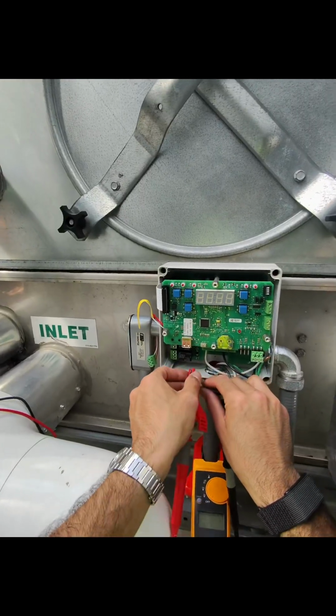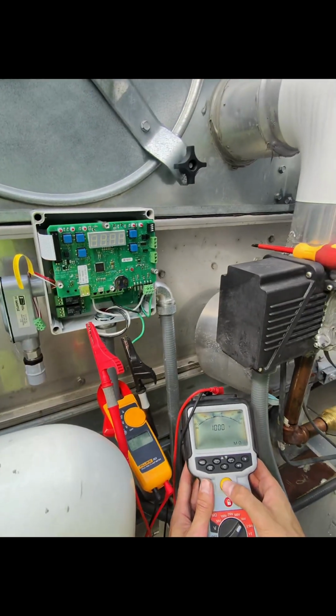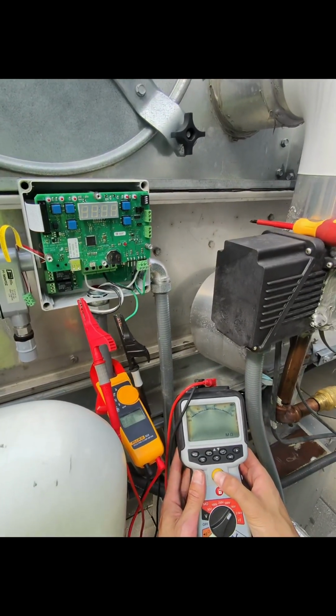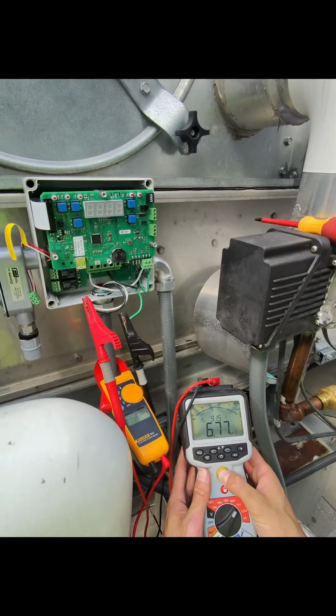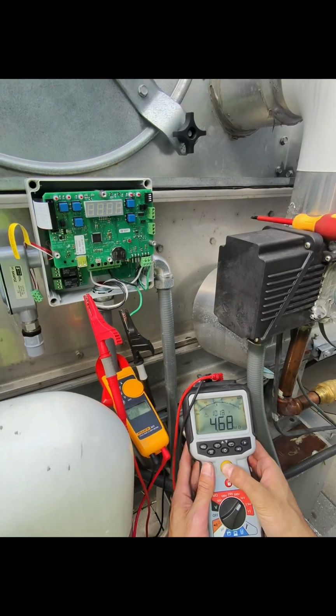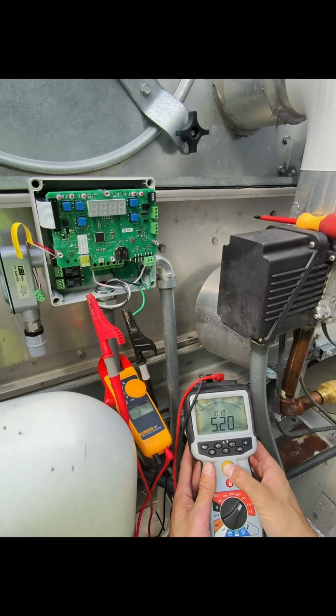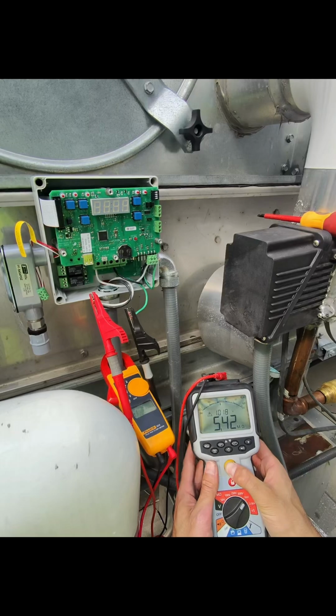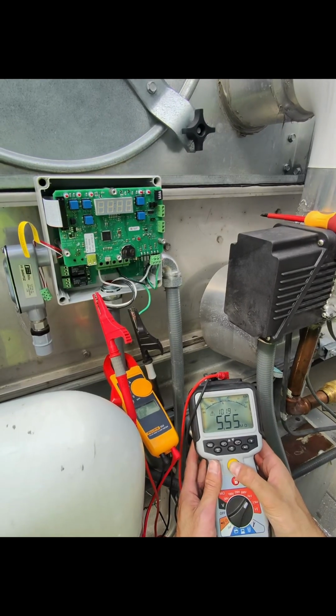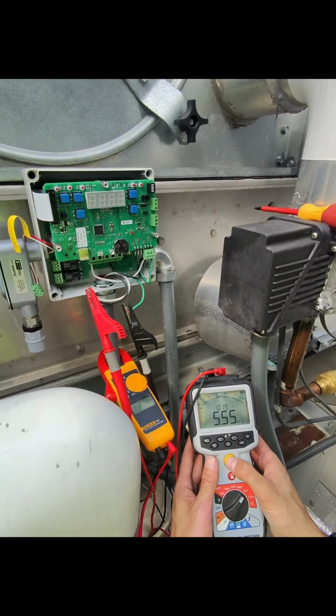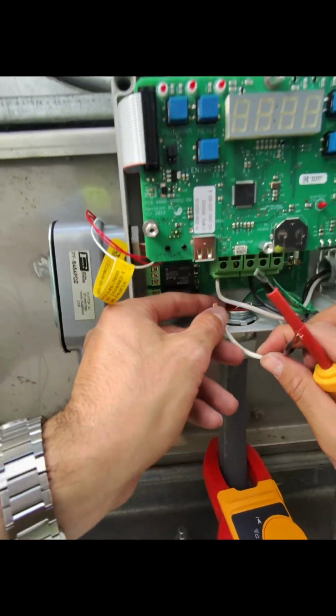Connect the black lead of your tester to the ground and the red lead of your tester to the power wires of the heat trace cable. You can then test the cable at 1000 volts DC, and you're looking to get at least 5 mega ohms after insulation is installed over the heat trace on the piping.